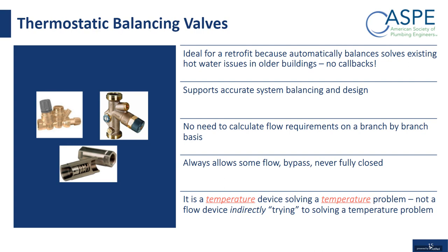Thermostatic balancing valves also support accurate system balancing and design, because you put the valve in the system and it's going to react the way you design it to act. If you're looking for a certain return temperature in your system, you're going to get that. You don't have to worry about whether the balancing valves are set correctly, and you don't have to calculate the flow requirements on a branch by branch basis. As long as you have the pump sized properly for flow and head pressure, these valves will, on an individual branch or riser basis, adjust their position to where they need to be to overcome the heat loss.